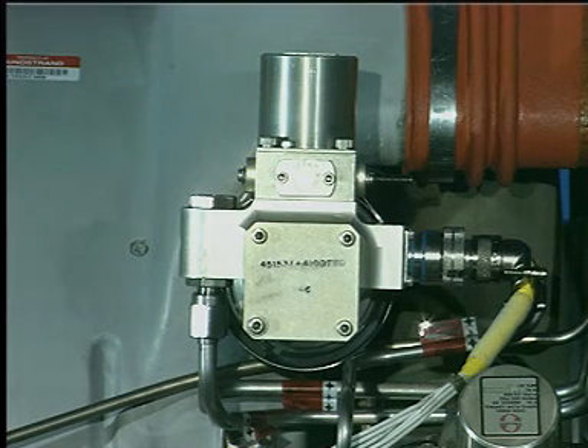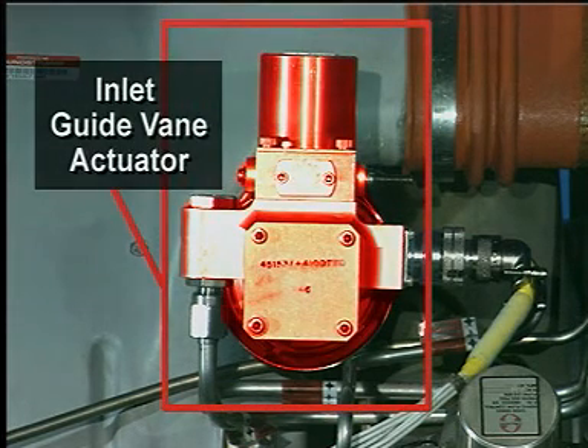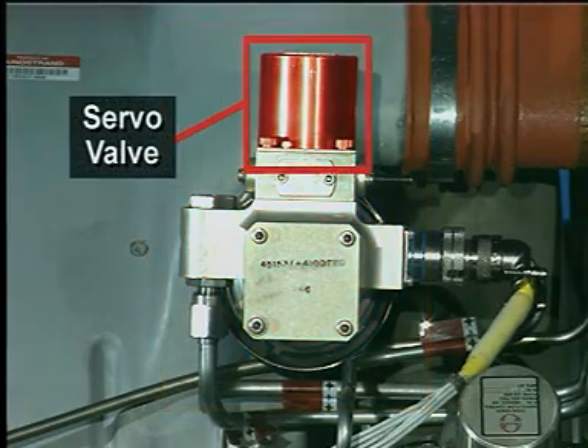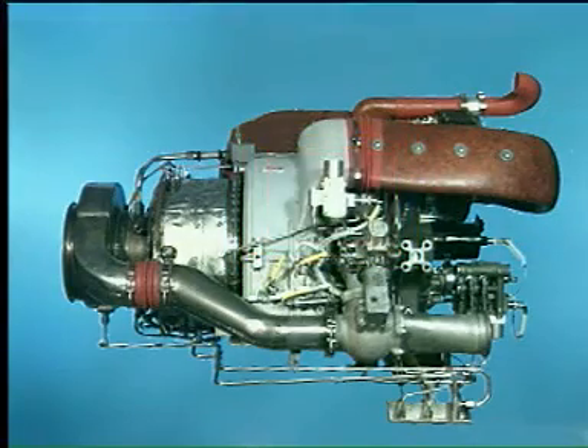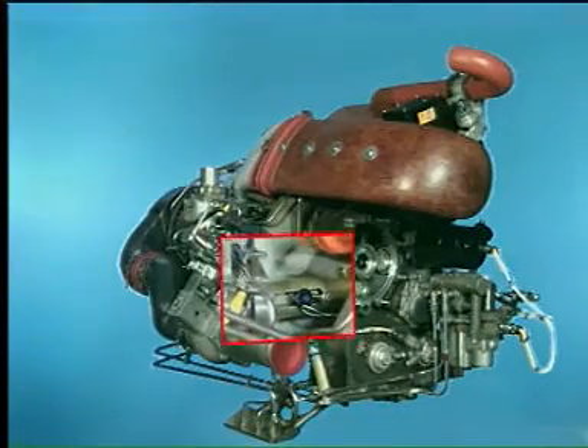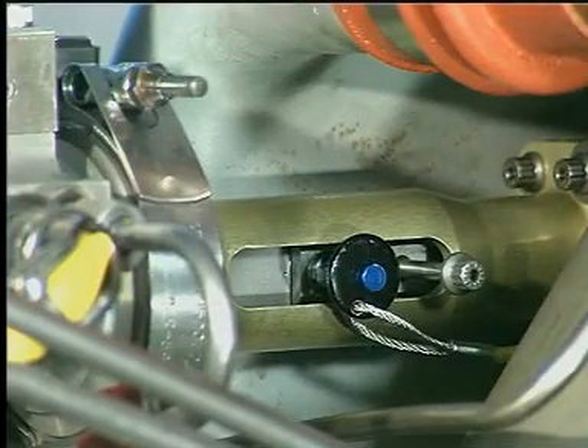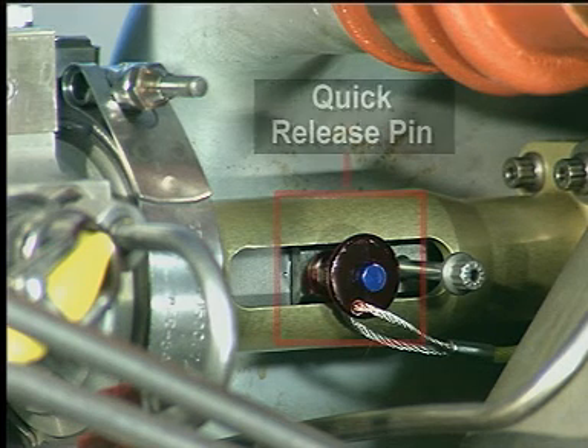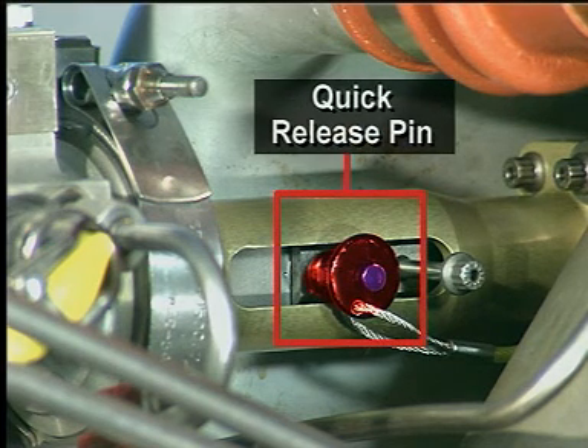The inlet guide vanes are operated by the inlet guide vane actuator located at the 3 o'clock position on the load compressor case. The inlet guide vane actuator is operated by servo fuel supplied from the fuel control unit pressure regulator. It is controlled by a servo valve. The actuator is connected to the operating rod by a quick release pin. The inlet guide vane position is monitored by an internal linear transducer.